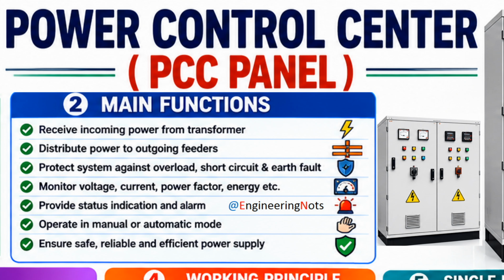If a short circuit or overload occurs, the protection system detects the fault and disconnects the affected circuit before serious damage can happen. The third function is power monitoring. Engineers can continuously monitor voltage, current, power, frequency, energy consumption, and power factor from this panel. The fourth function is safe isolation. Before maintenance begins, circuits can be isolated safely to protect personnel and equipment. In other words, the PCC is not just a distribution panel. It is also the control and protection center of the entire low-voltage electrical system.